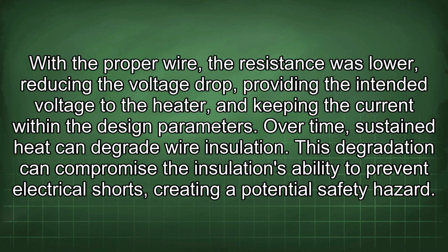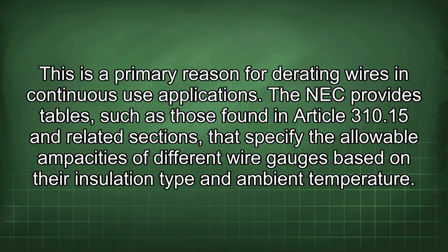Over time, sustained heat can degrade wire insulation. This degradation can compromise the insulation's ability to prevent electrical shorts, creating a potential safety hazard. This is a primary reason for derating wires in continuous use applications. The NEC provides tables, such as those found in Article 310.15 and related sections, that specify the allowable ampacities of different wire gauges based on their insulation type and ambient temperature.